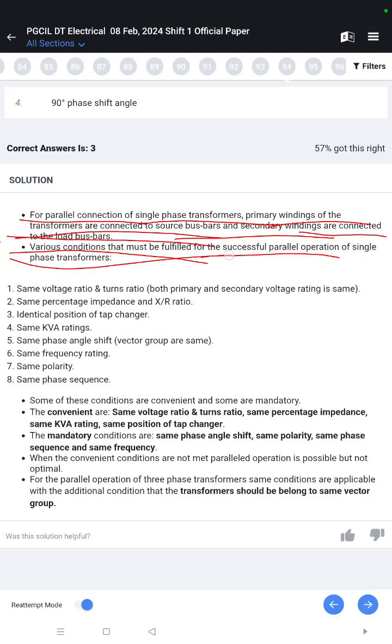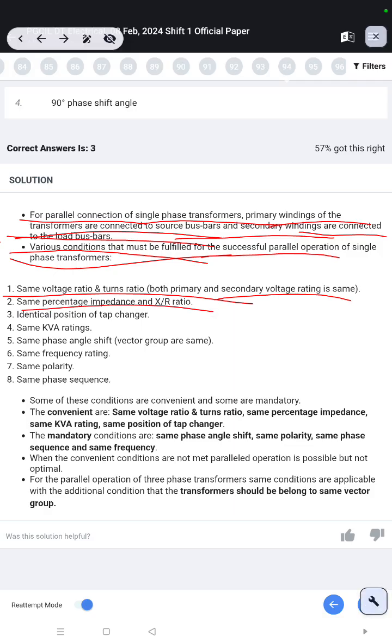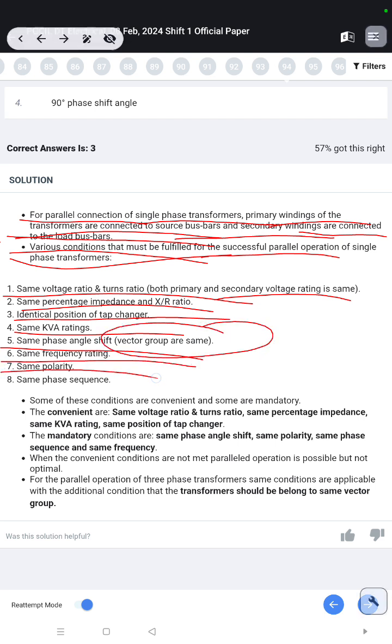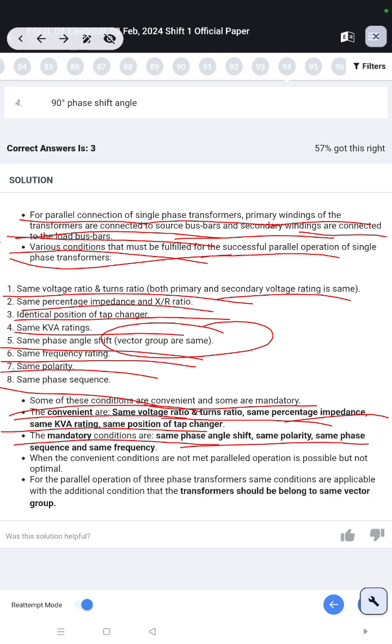Same voltage ratio, turn ratio, both primary and secondary voltage rating the same, percentage impedance and X by R ratio, identical position of tap changer, same kVA rating, same phase angle shift, vector group same, frequency rating, same polarity, same phase sequence. Some of these conditions are convenient and some are mandatory. The convenient ones are same voltage ratio, turn ratio, same percentage impedance, same kVA rating, same position of tap changer. The mandatory conditions are same phase angle shift, same polarity, same phase sequence and same frequency. When the convenient conditions are not met, parallel operation is possible but not optimal. For the parallel operation of three-phase transformers, the same conditions are applicable with the additional condition that the transformers should belong to the same vector group.